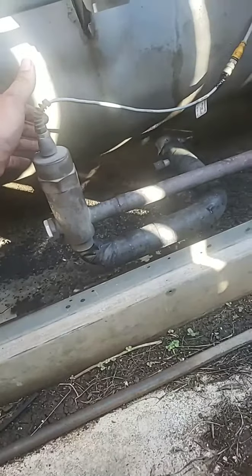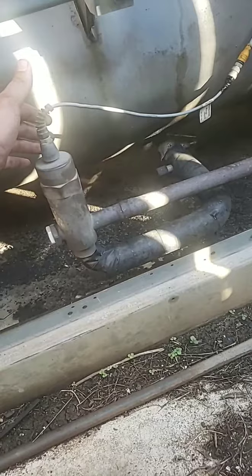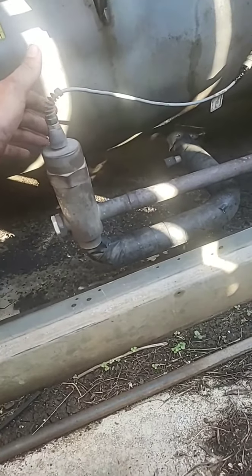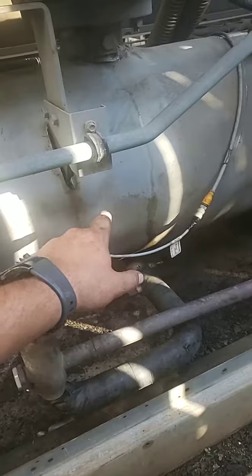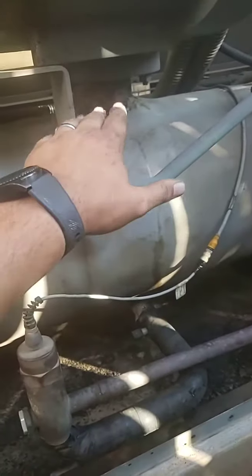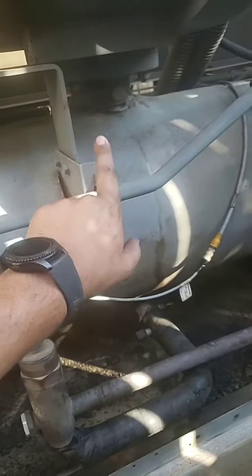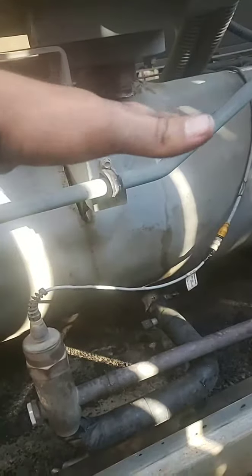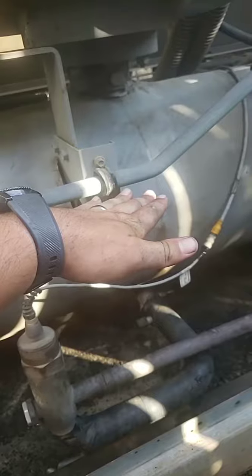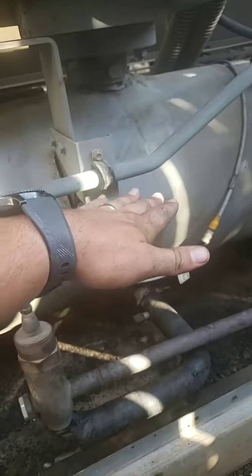Now, let's see, I want to make sure I cover everything. So that's just your basic operation here. We're coming in, like I said, it comes in and hits the evaporator. As it boils off, that's our suction coming into the bottom of the compressor there. The compressor actually sits on top of the suction flange and bolts down.